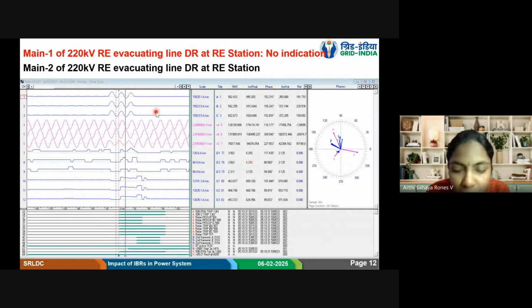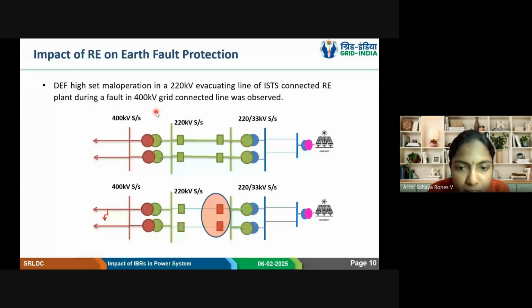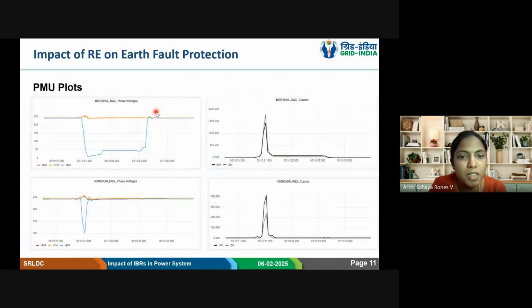So even though the fault is there in only one phase, in this case there was a fault in B phase. The fault was in a 400 kV line connected to Devanahalli substation. So what we see here are the PMU plots. In that particular line, due to the presence of an auto recloser, that particular faulty phase lost voltage, and then it has reclosed.